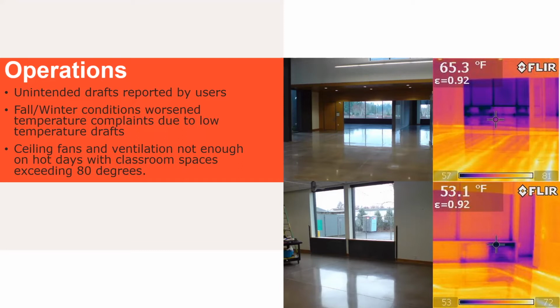Debris tends to be the biggest issue when you have floor stuff, but this was mostly air coming in because of our turbine ventilators. We did have enough debris building up from the screens on the outside, so you're still going to have an architectural screen for debris outside. I think now you'd also employ a sort of rain screen to try not to bring water too far in. Fall and winter conditions really worsened everything, and even in summer, though less used, there'd be dust since there are no filters. So if somebody's mowing the lawn or creating dust outside, you hit the override and close it. But it shouldn't be open too much in summer anyway, unless your temperatures are 70 to 75 degrees.